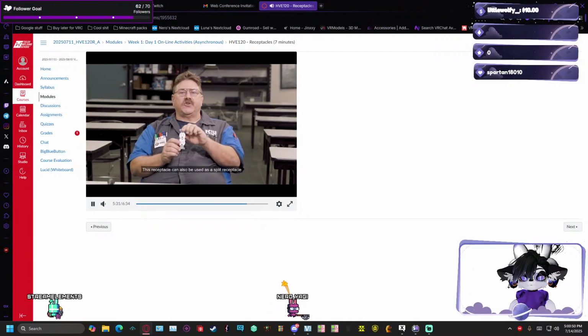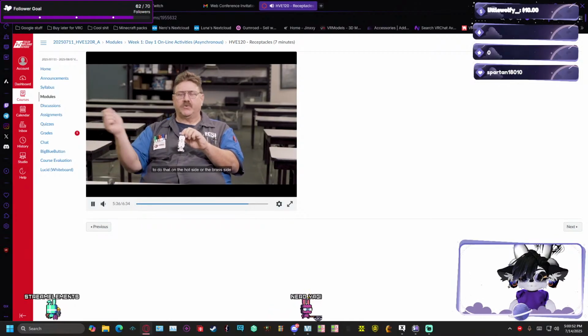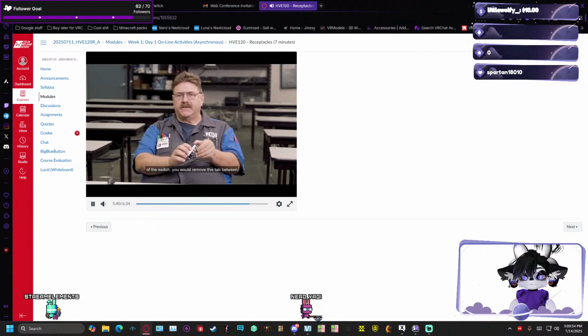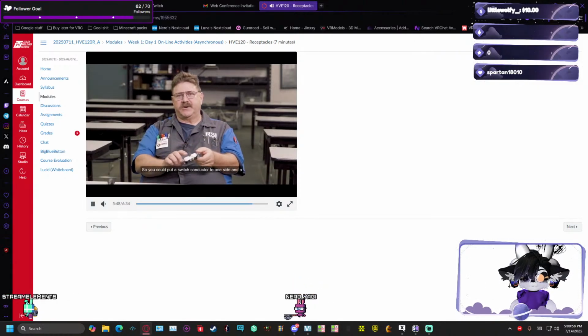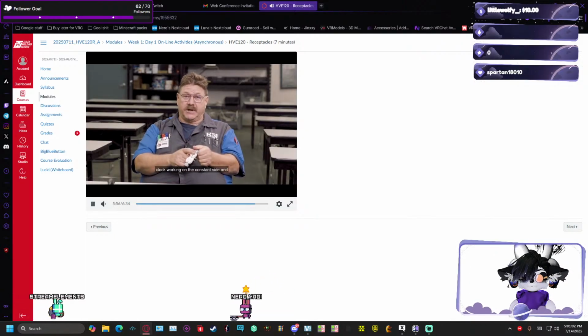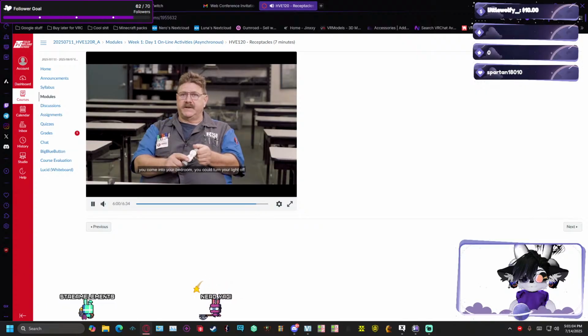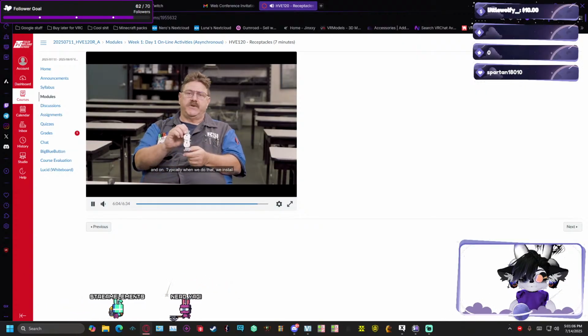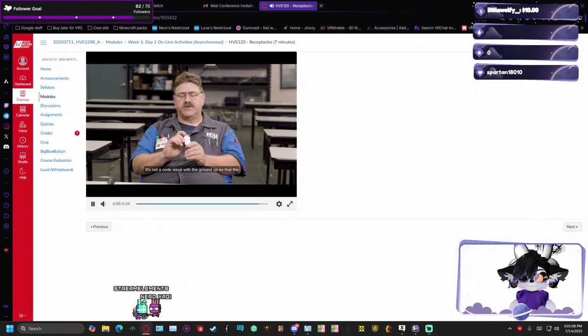This receptacle can also be used as a split receptacle so that you can control it with a wall switch. To do that, on the hot side or the brass side of the receptacle, you would remove this tab between the top and bottom screw, and that would isolate this part of the receptacle from the other, so you could put a switch conductor to one side and a constant conductor to the other side. That way you would have your alarm clock working on the constant side and your table lamp plugged into the other side, so that when you come in your bedroom, you can turn your light off and on. Typically when we do that, we install these with the ground up, and this is an industry standard, it's not a code issue, so that the homeowner or customer would know that receptacle is different, and that's where they want to place their table lamp.